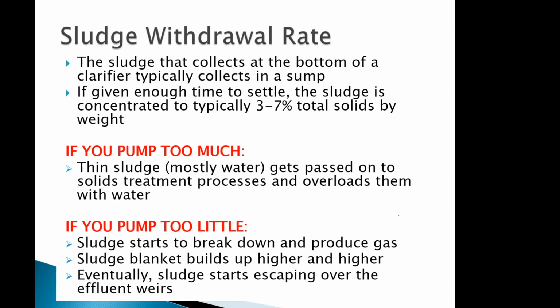So it's really important not to just let the pump pump. You're usually going to have it on a timer where it turns on and off periodically to allow time for the sludge to concentrate, so that we're pumping more sludge to the next process and less water. But on the other hand, if we pump too little, then that sludge that's just sitting there is going to start to break down, go anaerobic, and produce gas. That can cause odor issues, that can cause poor settlement.